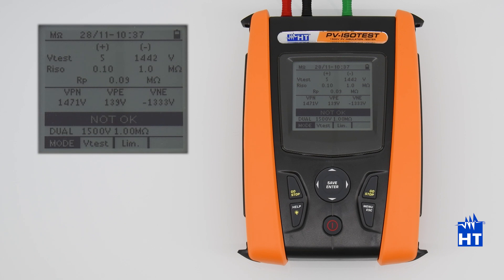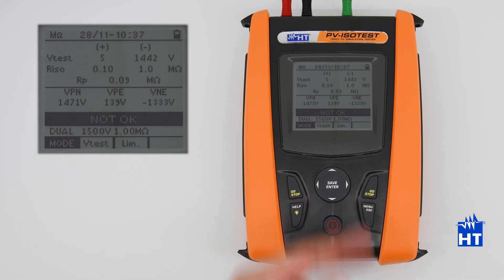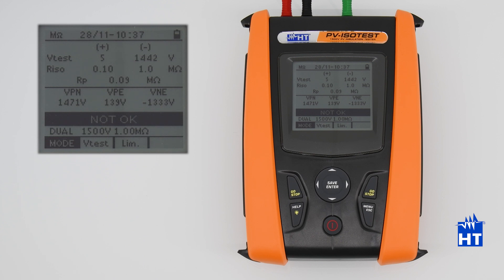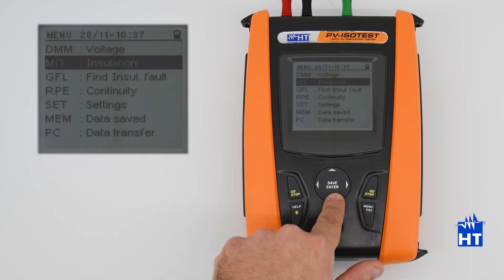Ground fall locator function. We have just performed an insulation measurement. As you can see, we have a pretty good insulation between negative pole and earth, but absolutely bad insulation between positive and earth. After performing the test, we can go on the menu and select the find insulation fault.